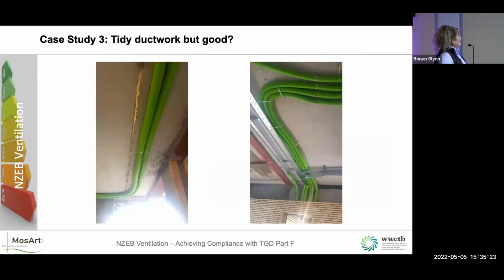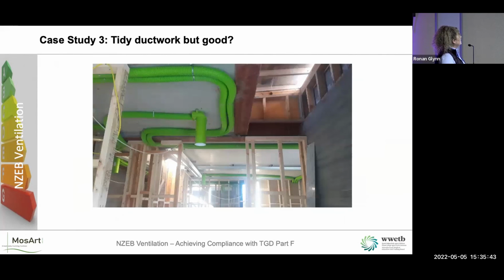This is a better install of ducting. Okay, so it seems nice and tidy there, but at the same time, we want slow sweeping bends on it, right? So we want to get from A to B in the shortest run of ducting as possible. So this duct is nearly running back on itself. So if you take out those bends, the fan won't have to work harder. You can turn down your fan a little bit. Again, same here. It looks lovely and tidy, but at the same time, we could tidy up on the ducts, make the ducts a lot shorter.